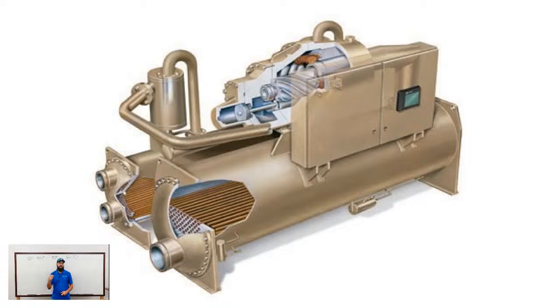If you're running a lead-lag system with multiple chillers, then usually the lag chiller won't engage until the lead chiller has reached 100% capacity or RLA, and it needs to call for the second one. Or with a building automation system, if the chiller cannot maintain the chill water set point within a couple of degrees dead band for say 30 minutes, we're talking extended delay times here on staging.